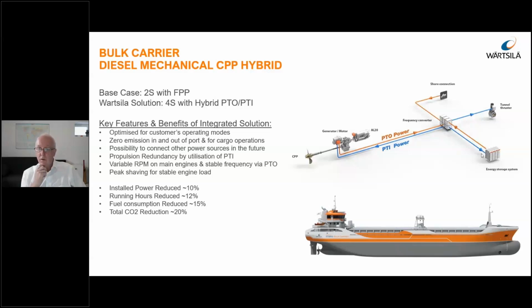And finally, we have a shore connection coming into here. Why do we do that, you may ask? Well, this vessel goes into ports which have either 50 or 60 hertz on the shore supply, and the vessel wants 60 hertz. So when we're connected up at a 50 hertz port, we connect it into this converter, and we convert that from 50 hertz to 60 hertz and export it to the main switchboard.